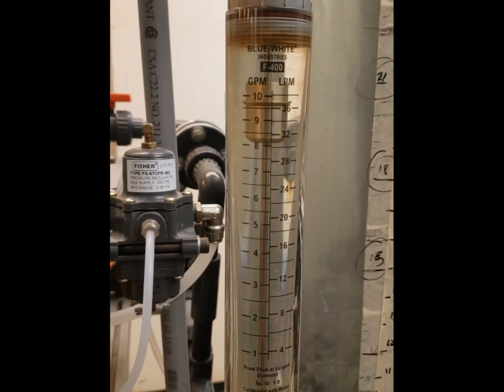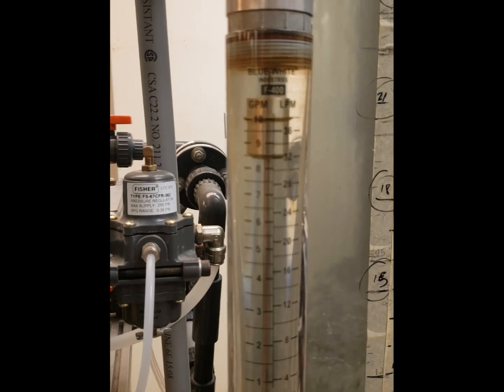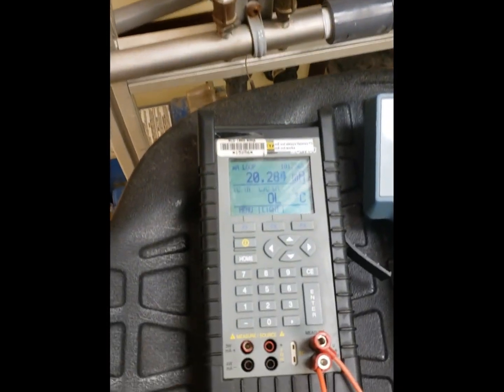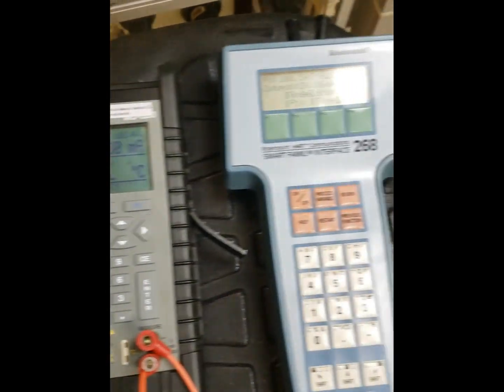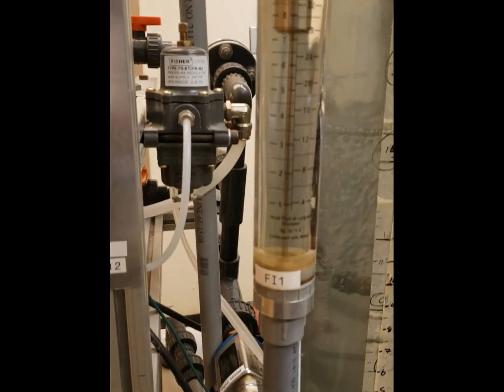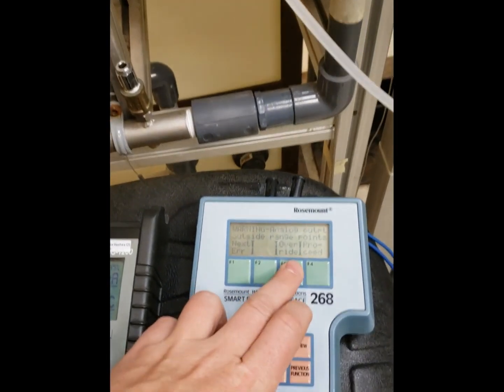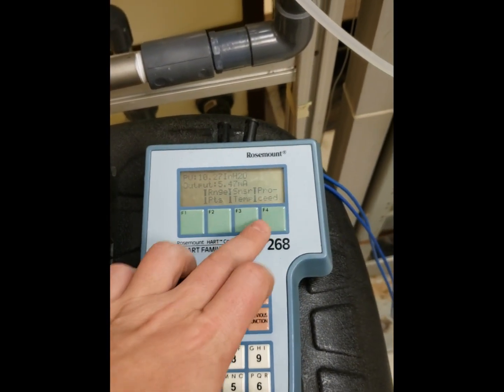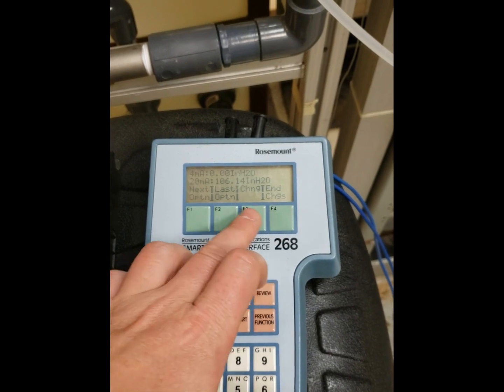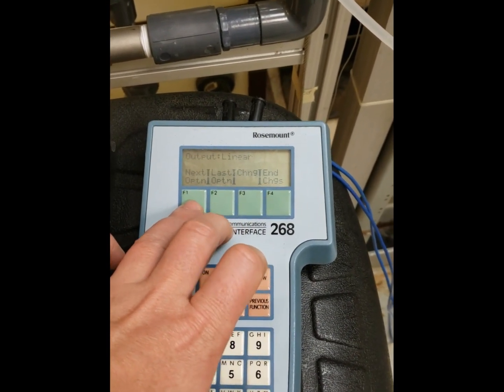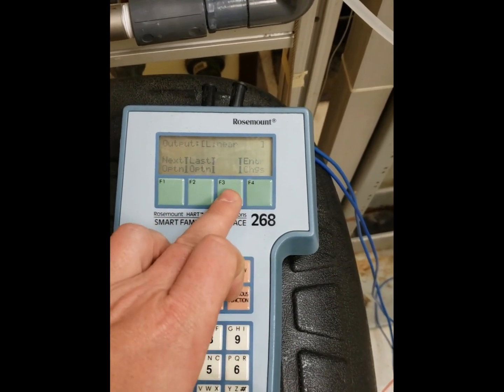And now we go up to a hundred percent, and a hundred percent flow gives us a hundred percent output. Now this is in the linear function. That is why we need to have a square root extractor. So now let's quickly save that from going out of range. Let's quickly go to our HART communicator and let us change our output from linear to square root.